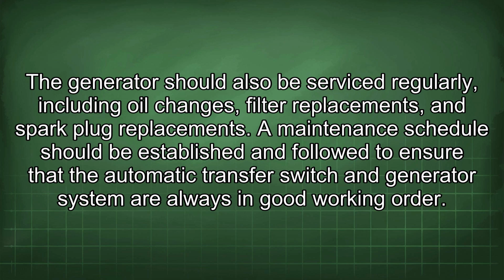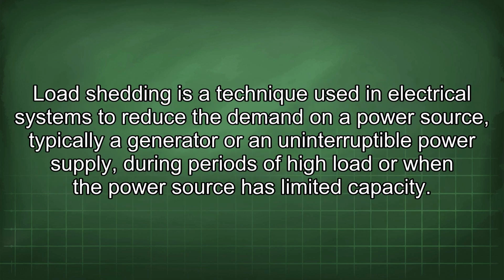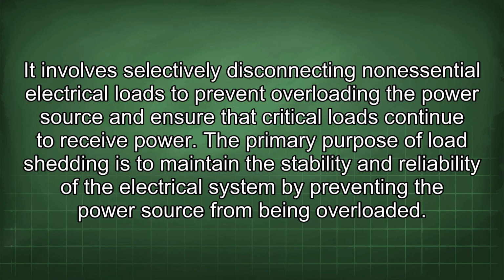Load shedding is a technique used in electrical systems to reduce the demand on a power source, typically a generator or an uninterruptible power supply, during periods of high load or when the power source has limited capacity. It involves selectively disconnecting non-essential electrical loads to prevent overloading the power source and ensure that critical loads continue to receive power. The primary purpose of load shedding is to maintain the stability and reliability of the electrical system by preventing the power source from being overloaded.